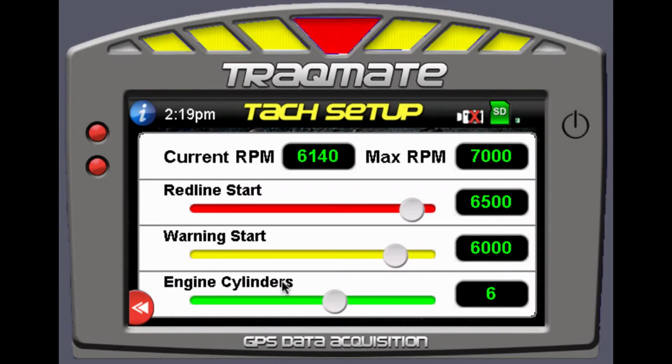You also may have to adjust it from electronic to coil, and you do that by actually popping open that little TraqDash USB box, and there's a micro switch within that to change from E to C, E being electronic, C being coil. You would need a fine, like an eyeglasses screwdriver or something very, very small to flip that micro switch in there, and there's actually a little piece of tape on top of it. But if you have the RPMs displayed properly, you won't need to do that. But if you see 0 RPMs and everything's hooked up right, then you may need to adjust that.